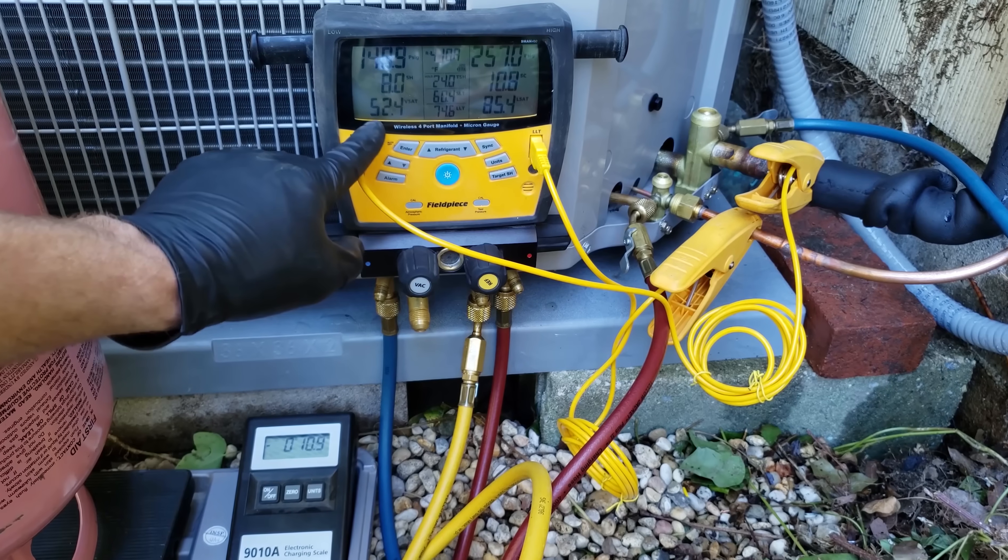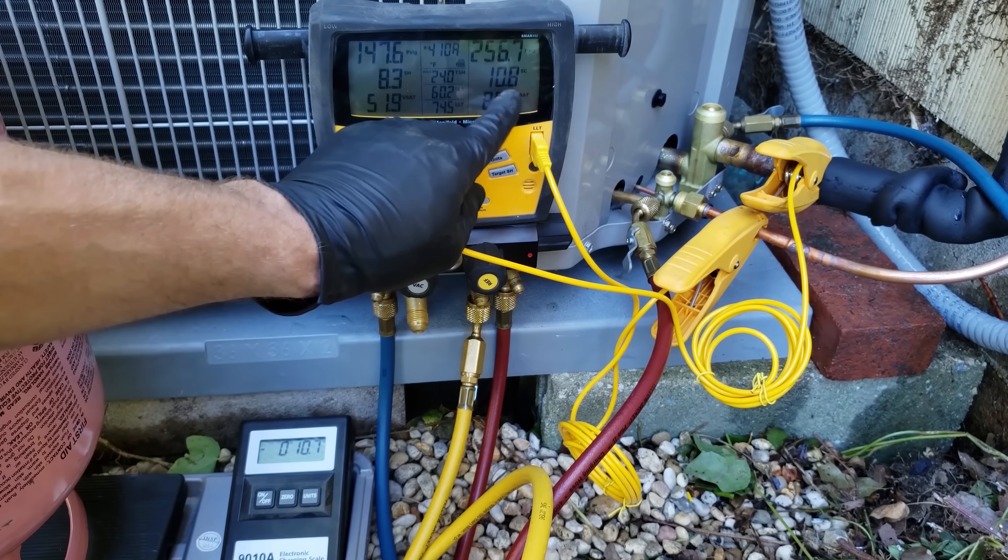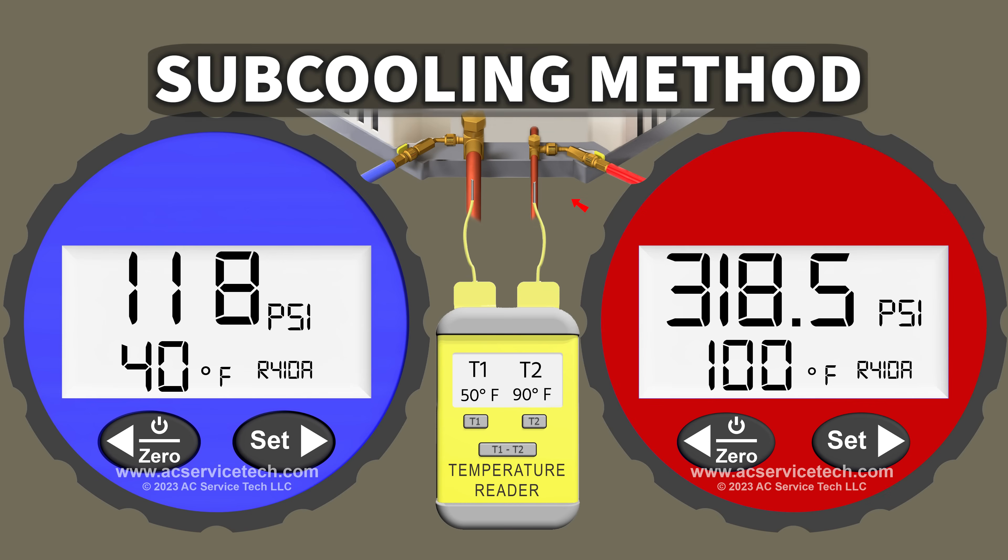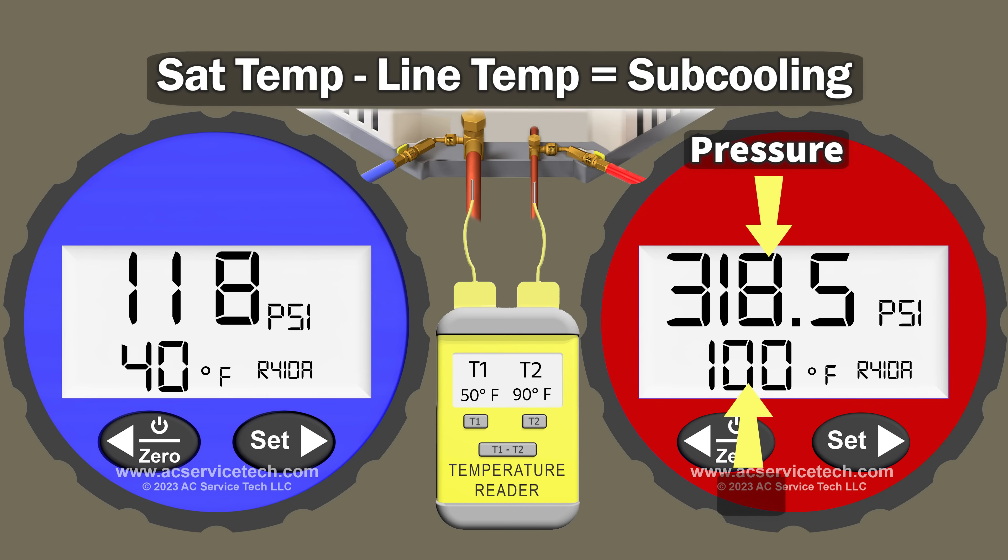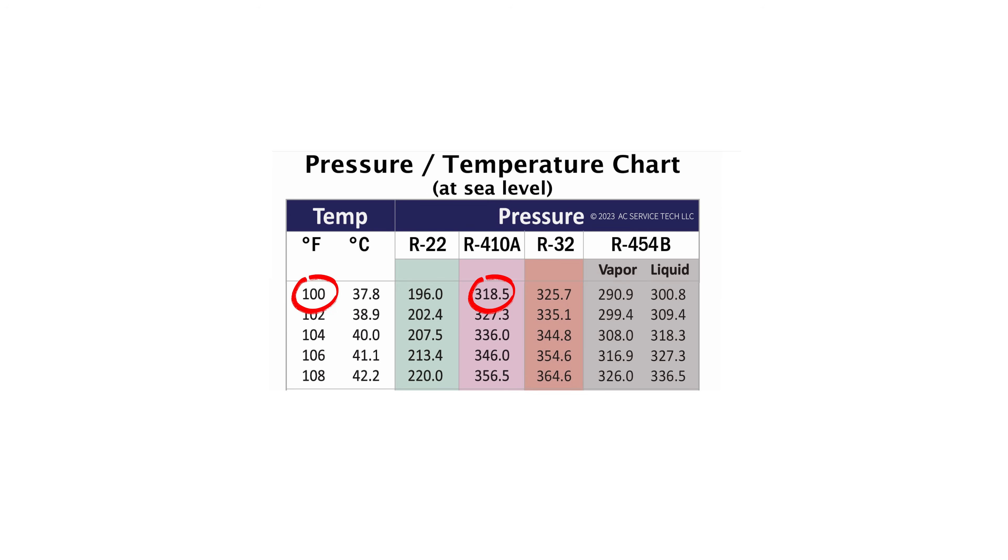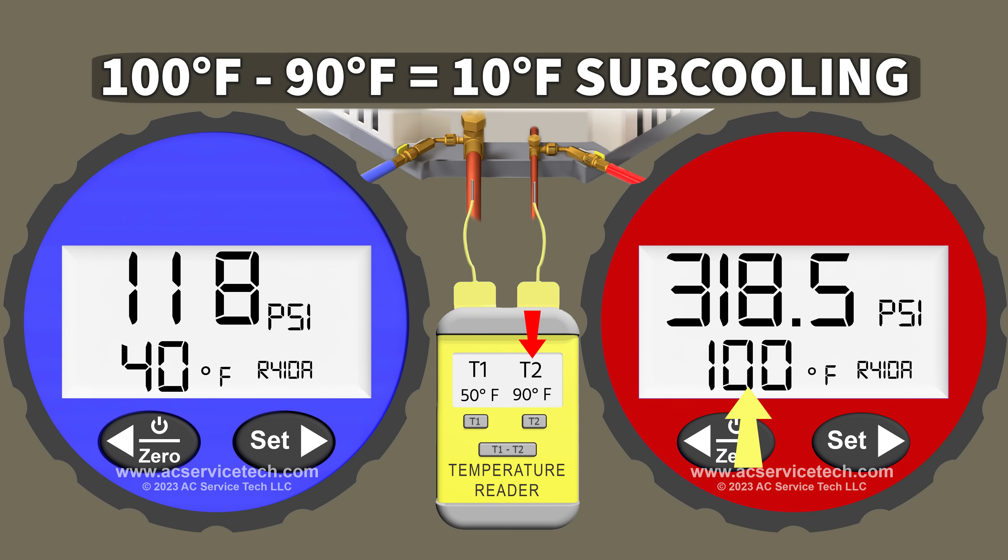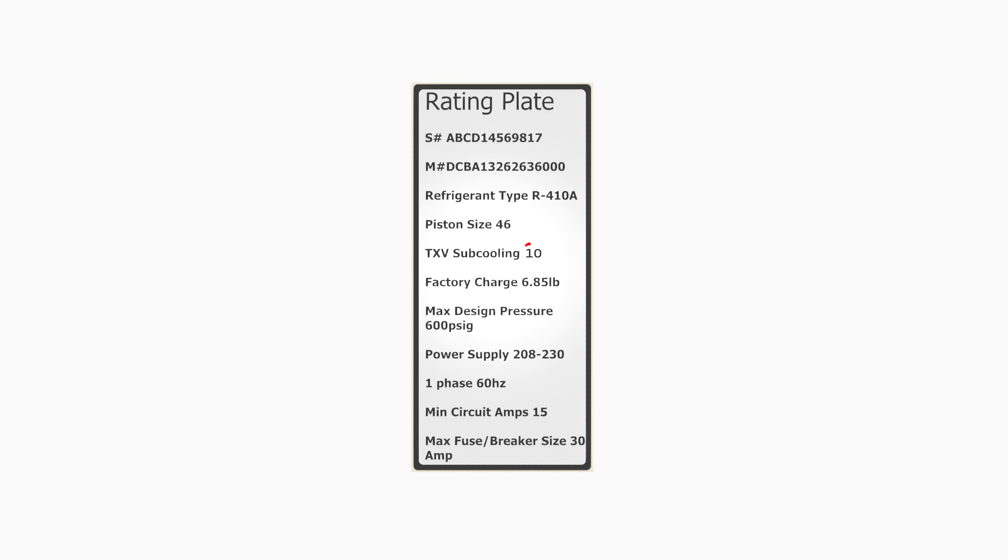After that, you're going to turn the system on and check the system's refrigerant charge with the subcooling method. That's on the small liquid line, and you measure the saturated temperature. You measure the pressure on the liquid line, convert it to saturated temperature, and you take that minus the line temperature. So if this was 100 degrees saturated temperature in the middle of the outdoor coil, and on the line it was 90 degrees, then you have 10 degrees of subcooling, and the refrigerant charge will be correct.